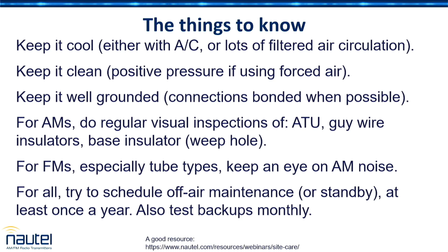So for every 10 degrees Celsius or 18 Fahrenheit, you double that lifespan. At 30 Celsius, or 86-88 Fahrenheit -- 86, I was right the first time -- you're at a 10-year lifespan. At 20 Celsius or 68 Fahrenheit, now you're at a 20-year lifespan. This is nominal -- back pressure will decrease it, running lots of air through and decreasing back pressure will increase it. But that's the basic rule of thumb.